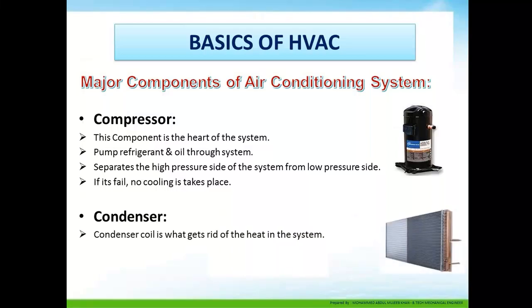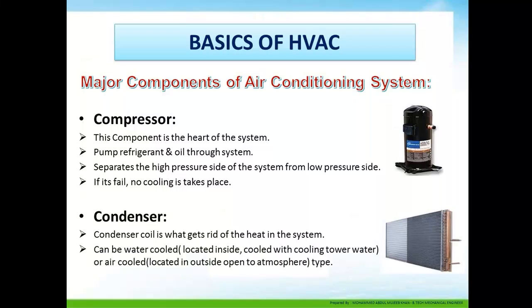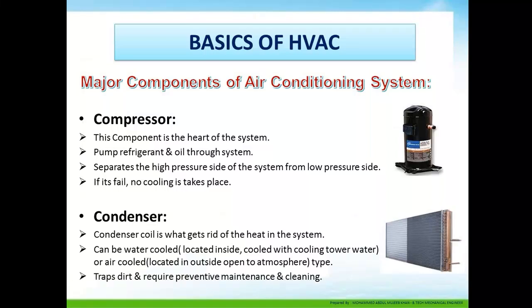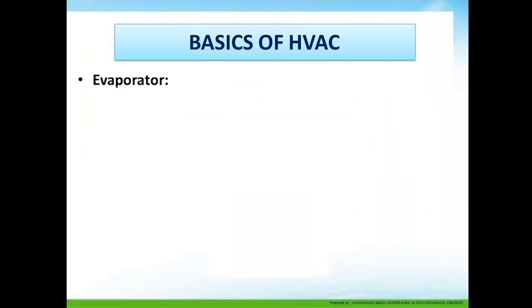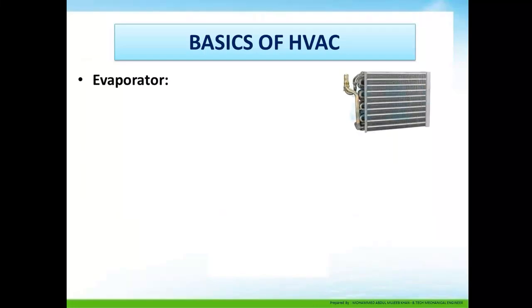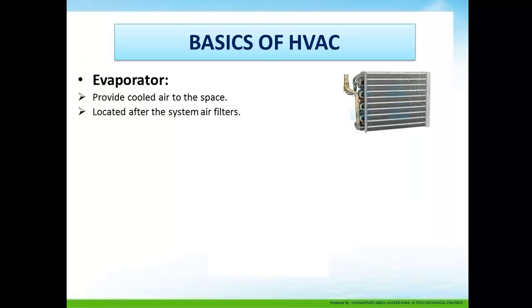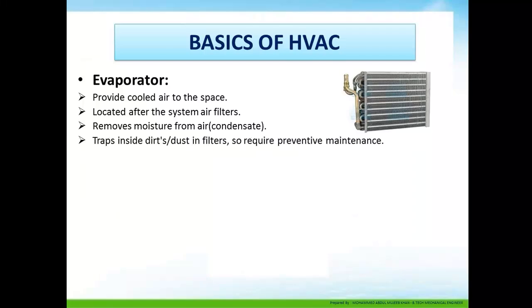The condenser coil gets rid of heat in the system. It can be water-cooled, located inside and cooled with a cooling tower, or air-cooled, located outside and open to the atmosphere. It traps dirt and requires preventive maintenance and cleaning. The evaporator provides cold air to the space, located after the air filters. It removes moisture from air and traps dust in filters, so it also requires preventive maintenance.